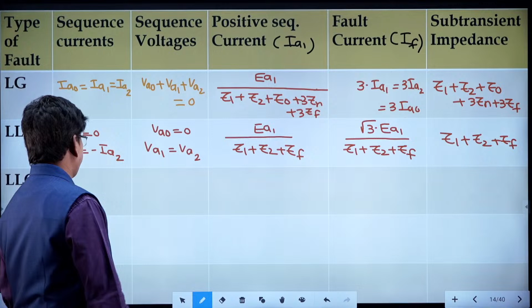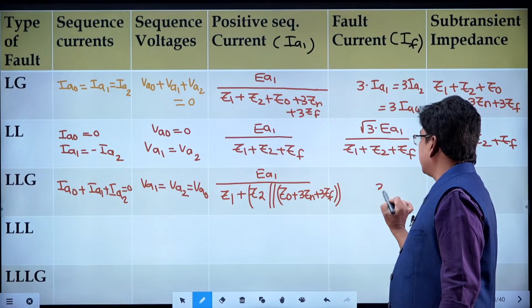In case of LLG fault, the current condition will be the sum of the currents IA0 plus IA1 plus IA2 is equivalent to 0. In case of the voltage condition, VA1 is exactly equivalent to VA2 is exactly equivalent to VA0. All the sequence voltages are same in case of LLG fault. And the positive sequence current will be EA1 divided by Z1 plus Z2 parallel to Z0 plus 3ZN plus 3ZF. That is the value of the positive sequence current, whereas the fault current will be 3 times IA0. So the subtransient impedance will be the same, Z1 plus Z2 parallel to Z0 plus 3ZN plus 3ZF.